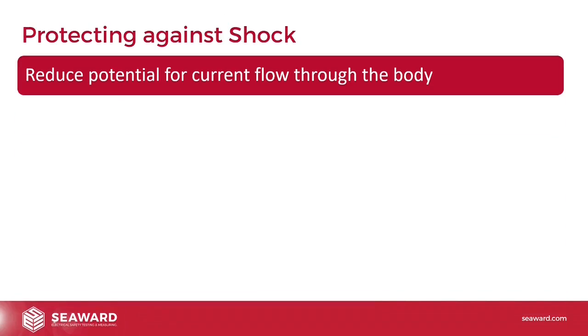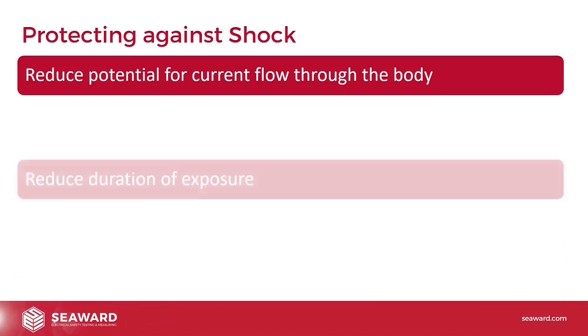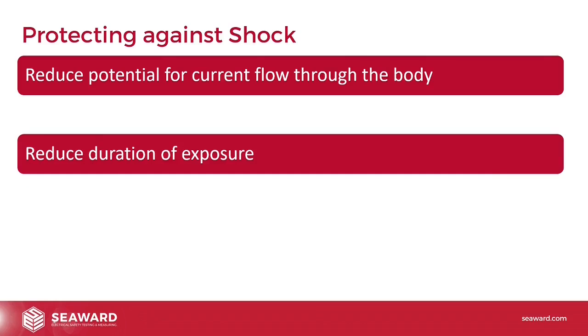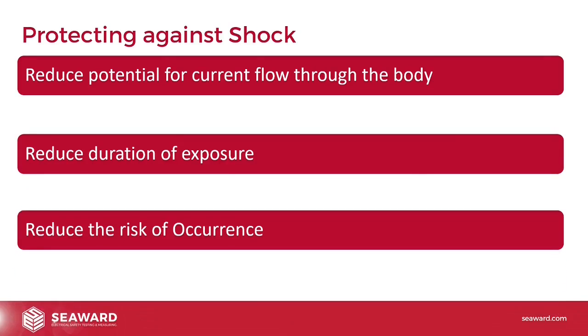So how are we going to protect against electric shock? We're going to reduce the potential for current flow through the body. We're going to do that by putting insulation in between you and it and making sure that you're isolated from ground. We're also going to reduce the duration of the exposure, so we're going to use things like safety shutoffs and RCDs to cut off the power if there's any leakage detected. And we're also going to reduce the risk of occurrence of a shock by training and letting people know kind of what the risks are and how to mitigate those risks.